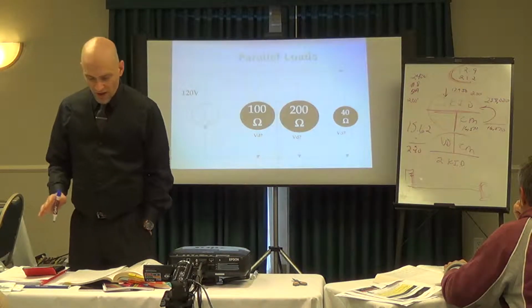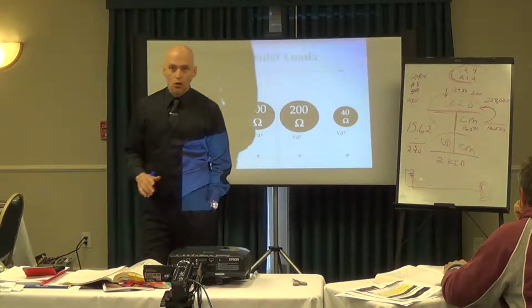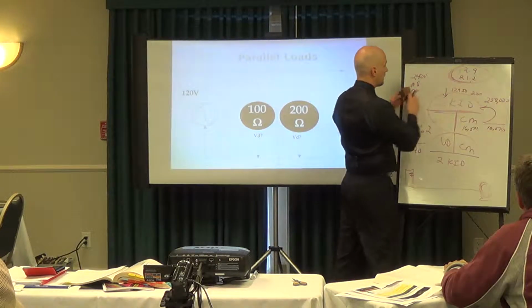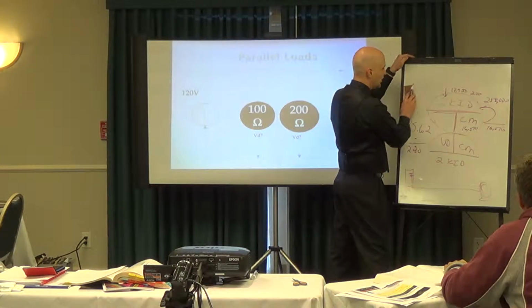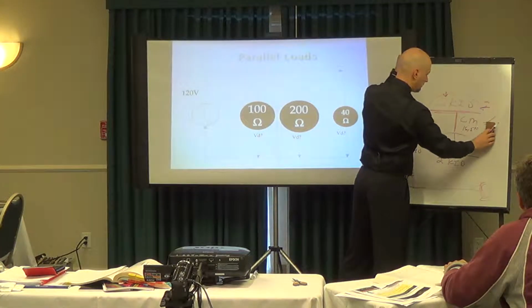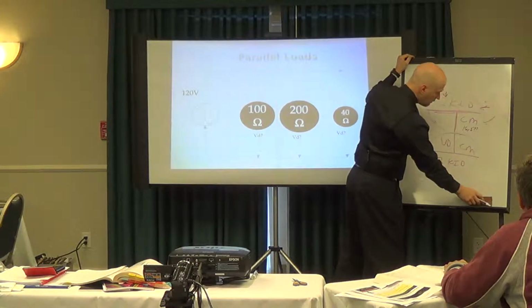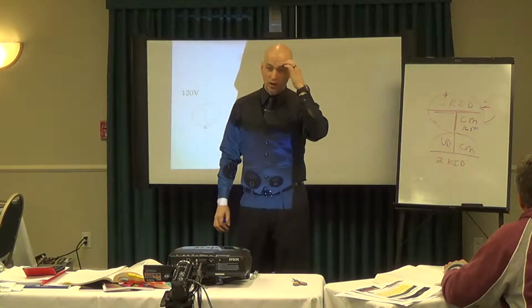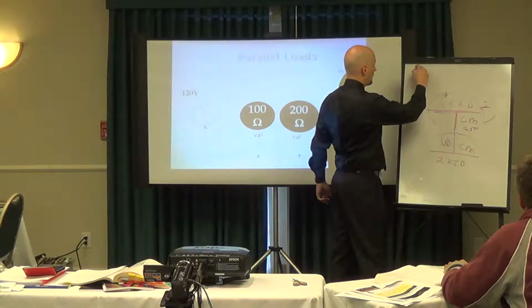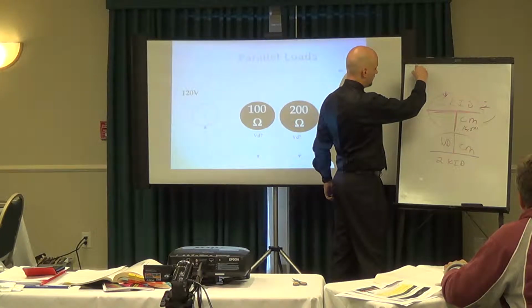So it's 6.5% then is the loss, which, here's what we're talking about, the voltage drop. If we're looking at a kind of a diagram, you're trying to see that the total value from your point of service to the very end of it, we don't want it to be more than 5%.